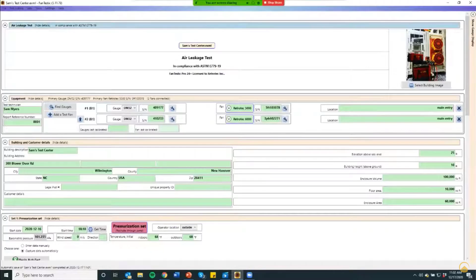So first off, what we want to do on our gauges is to make sure that they're all set on the wired settings. So if I go into my settings, all the way to the end, I can see network. And this one's on Wi-Fi Direct. I'm not running wireless, so I'm going to keep going through until it says wired. That way it knows to send a signal through, whether it's plugged into USB or Cat5 to the laptop. So once I have the software open and I have my equipment set up, like we just talked about before, I can just click and tell it to find gauges. Are you sure? Yes. And it's going to search for my connected gauges.